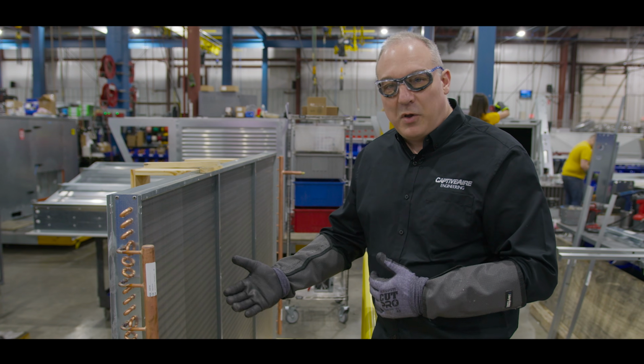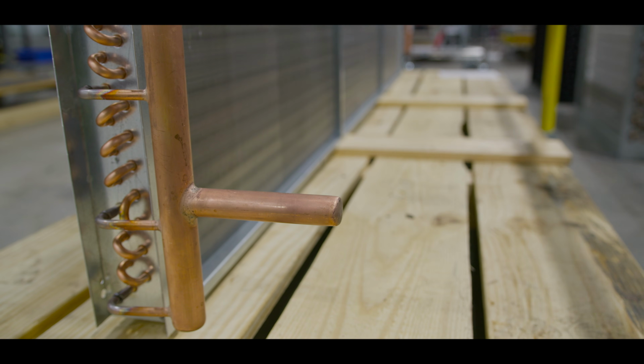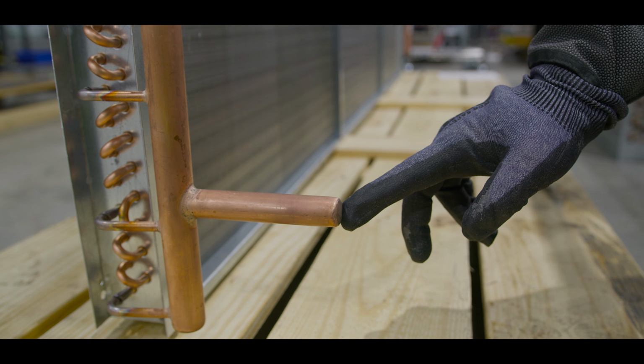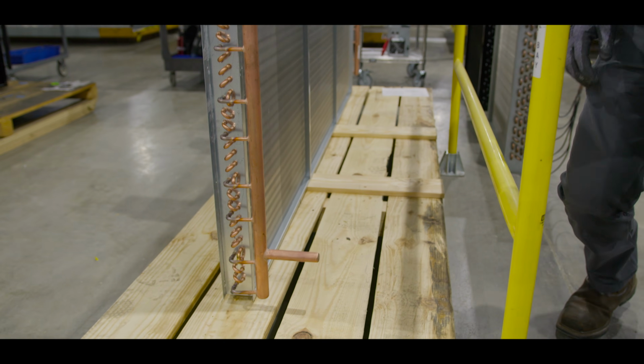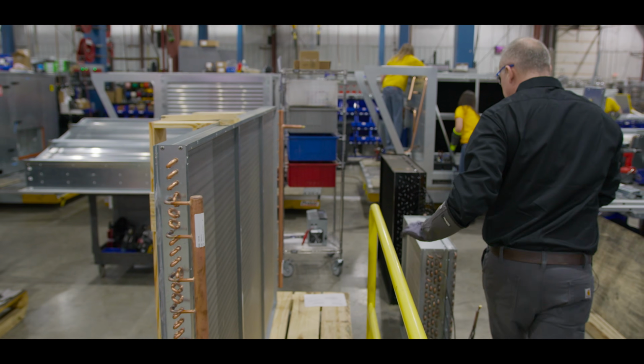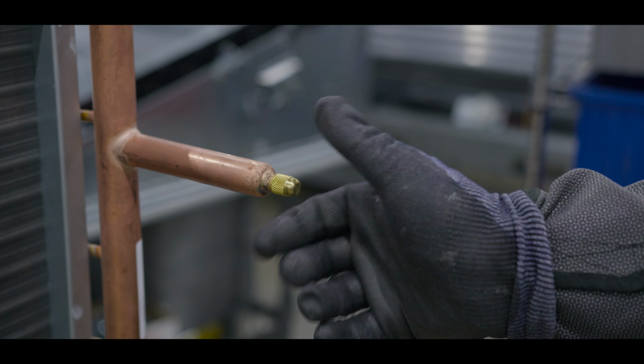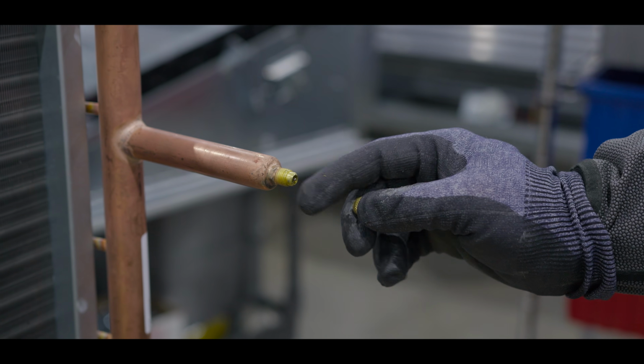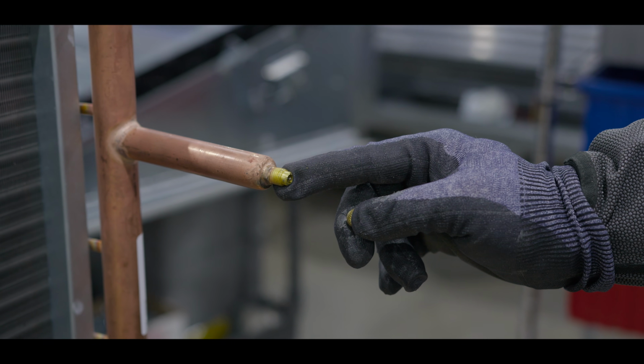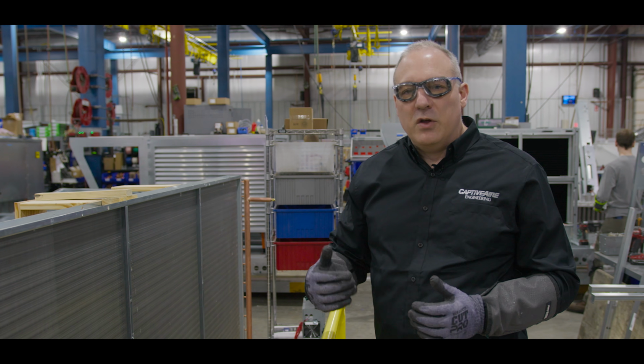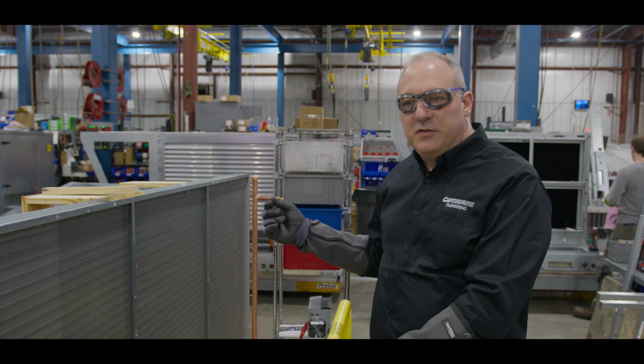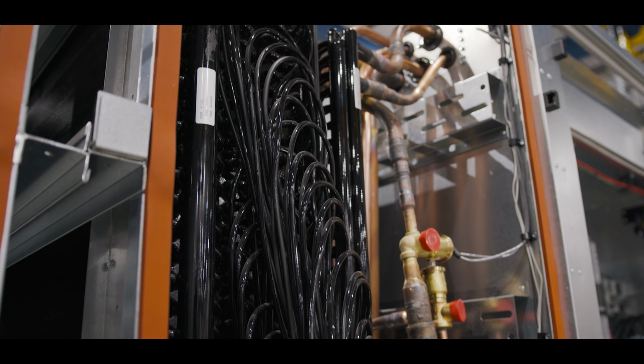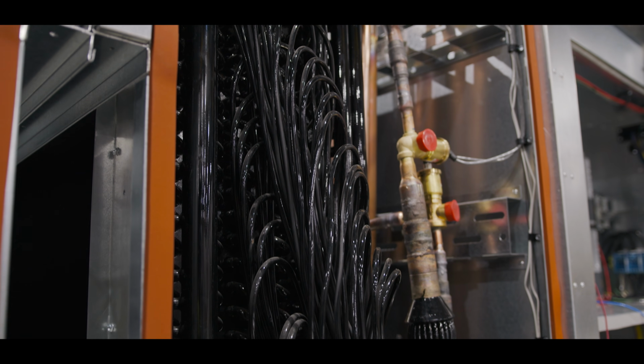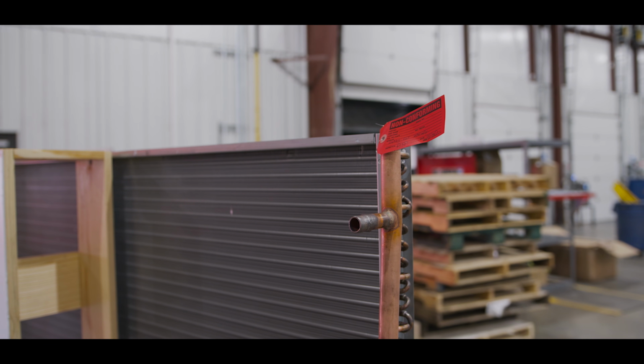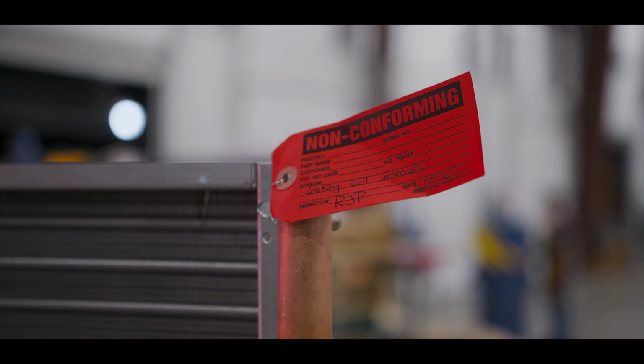We have worked with our suppliers to seal off the coils. You can notice here there's a seal, brazed shut on this end, and on the opposite end you can see there's a Schrader port. So our suppliers send the coils to us pressurized, and one of the first things we do before using the coil is check to make sure there's a minimum amount of pressure inside. If there's not pressure, we know there's a potential leak in the coil, and we know to take corrective action there.